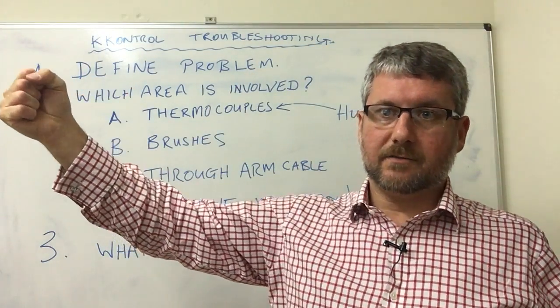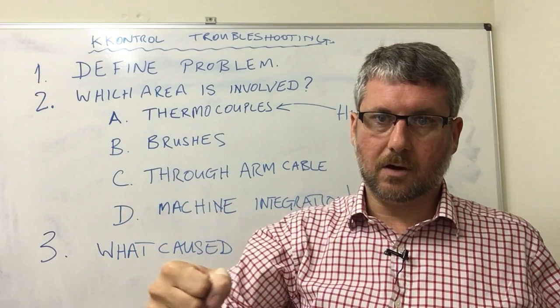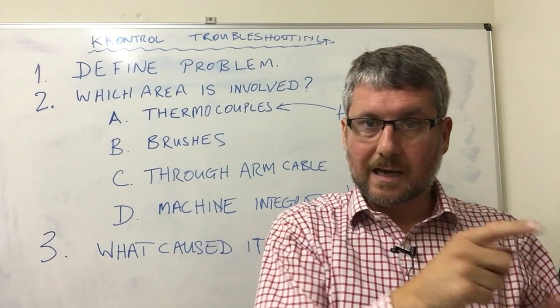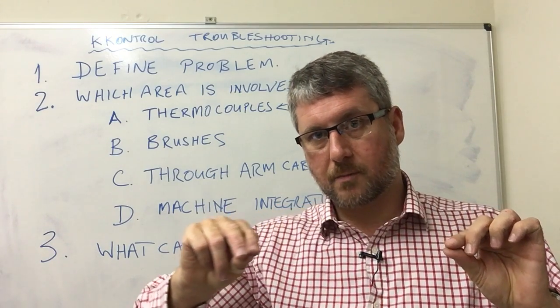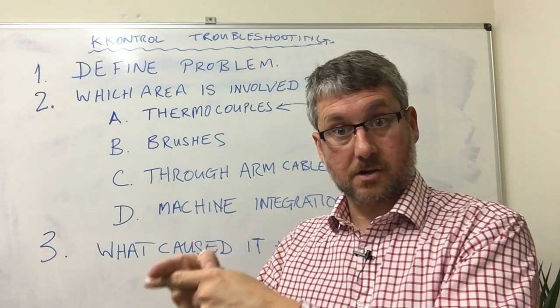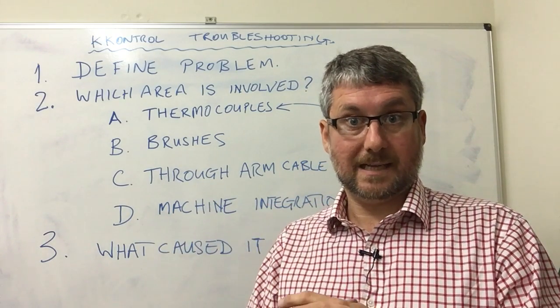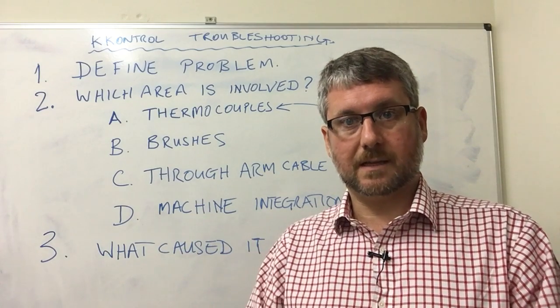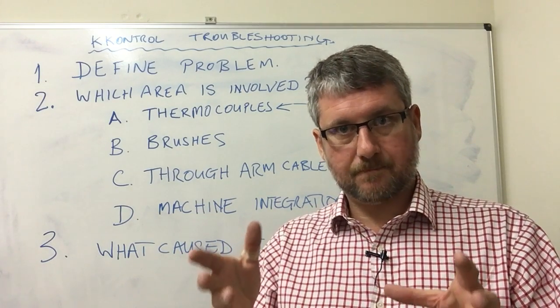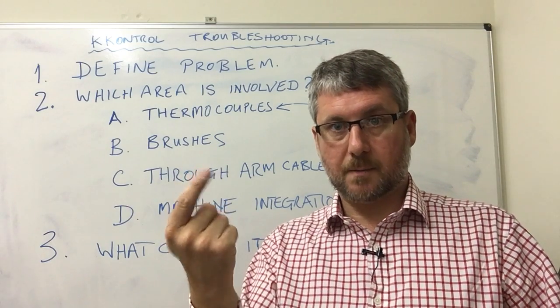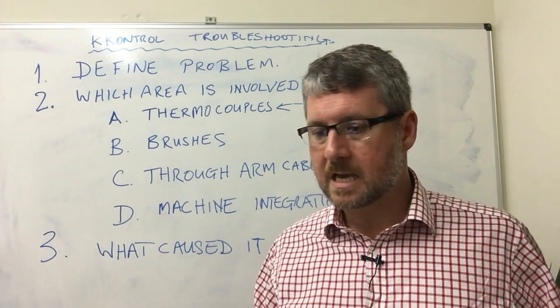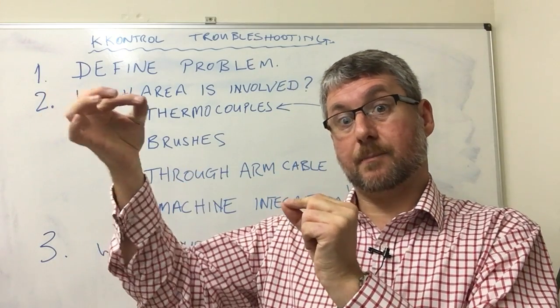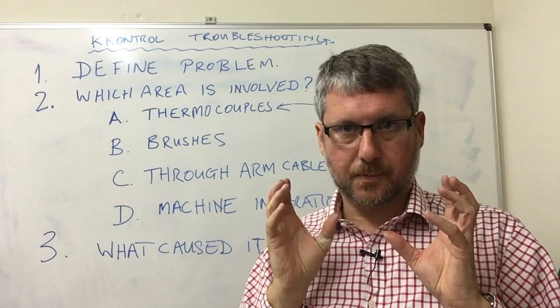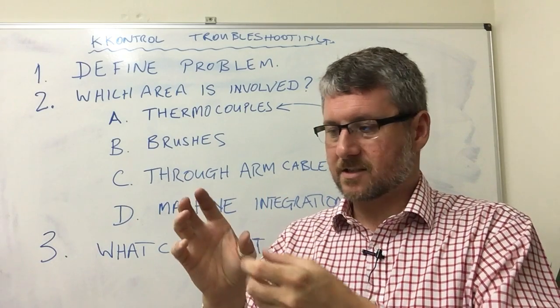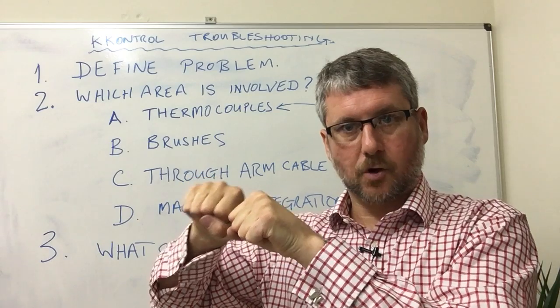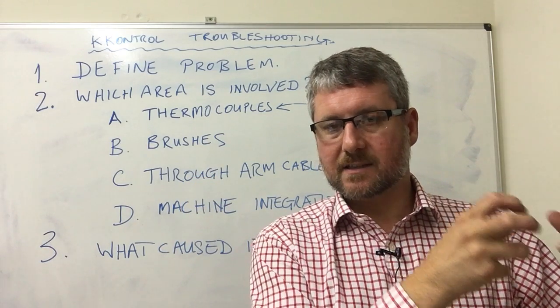So K-Cord software certainly would be a must for troubleshooting and checking the system. Take that hot air gun and run it down the full length of the thermocouple. What that will do is raise the temperature along the thermocouple wire. And if there are any short circuits there, your temperature will rise, and that will identify a fault in that thermocouple. And most of them, I say, are at the junctions where the cable of the thermocouple goes into the socket or the plug, and where the cable of the thermocouple goes into the back of the probe itself. So that's why on our production probes we have gone to great lengths to ensure there are good connections at the probe side and good connections at the plug.